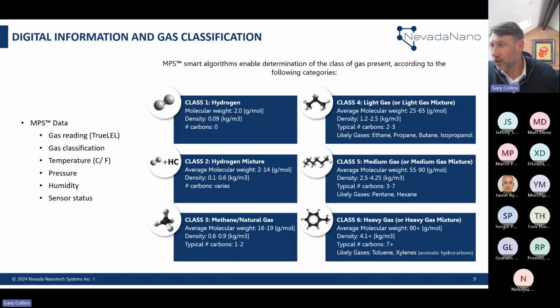This is really important. If you look at gas transmission, where you were traditionally just looking for hydrogen, you can also start to look at whether you're seeing hydrogen and effectively natural gas in classes 1 to 3. And if you're looking at other gases that might be present, such as propane and ethane, with a generic flammable reading, you can still start to distinguish between the different gases present. So it's really quite a data-rich sensor.